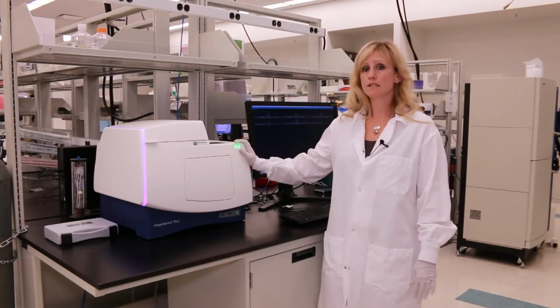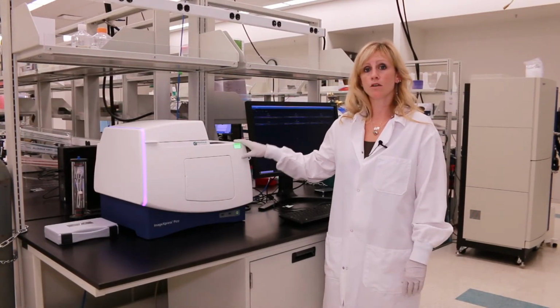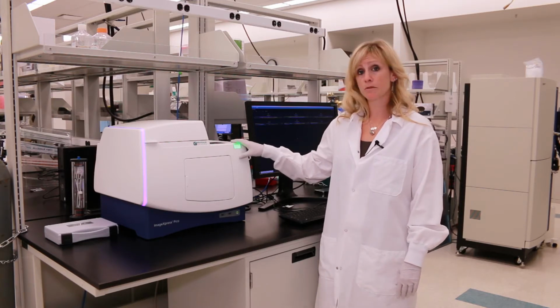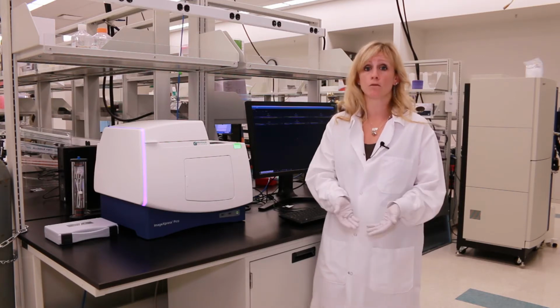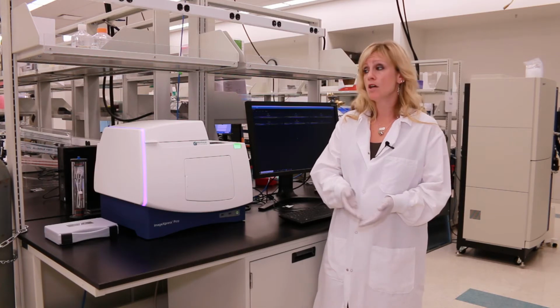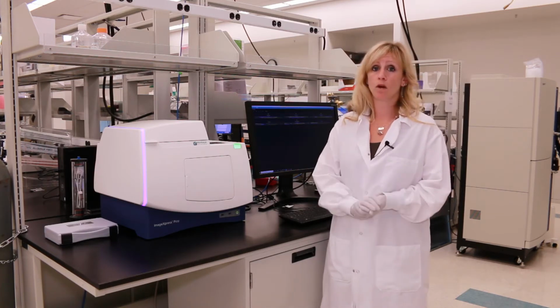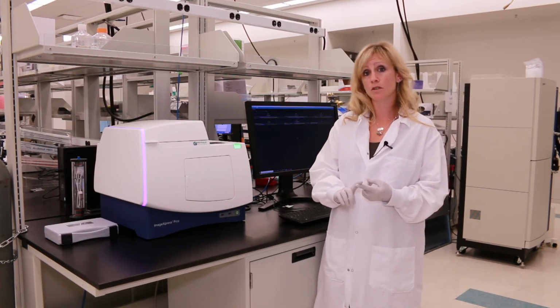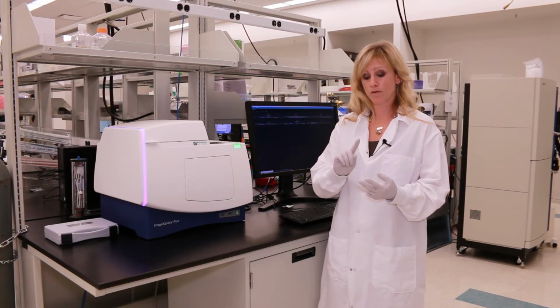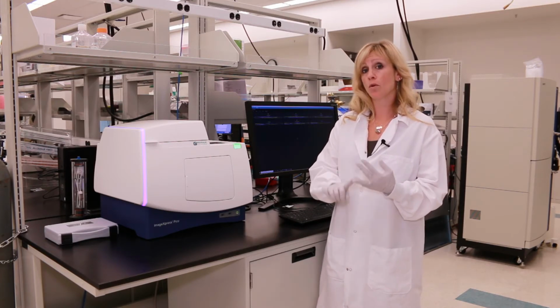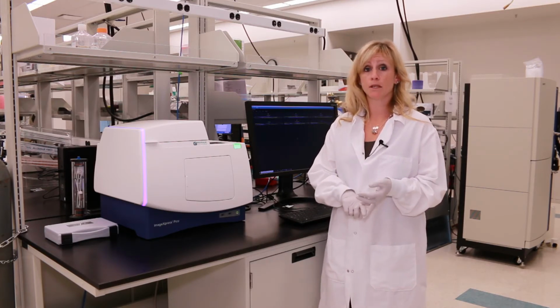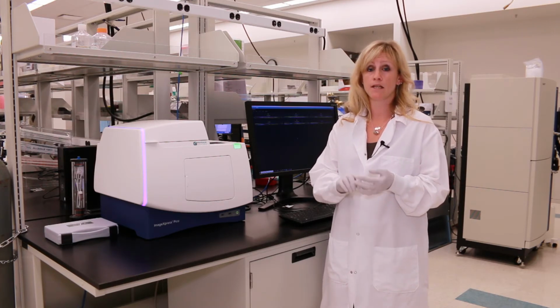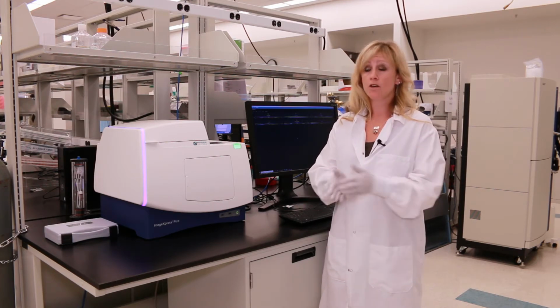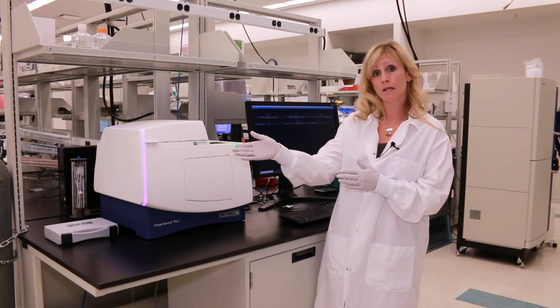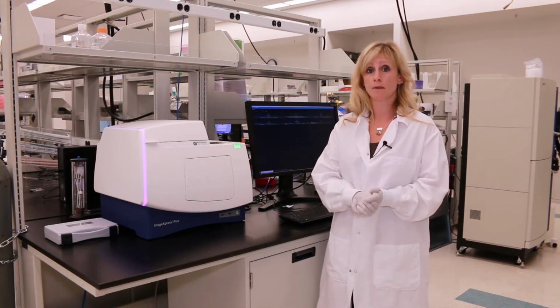One of the nice things about the ImageXpress Pico is you can configure it for your live cell imaging needs. So you can have temperature control up to 40 degrees Celsius, but also that 3-gas control that I talked about. So we're going to go to the back of the instrument where I'm going to show you inlets for CO2. There's also a port for compressed air, and then a port for nitrogen that allows you to deplete oxygen levels for experiments that need a hypoxic environment.